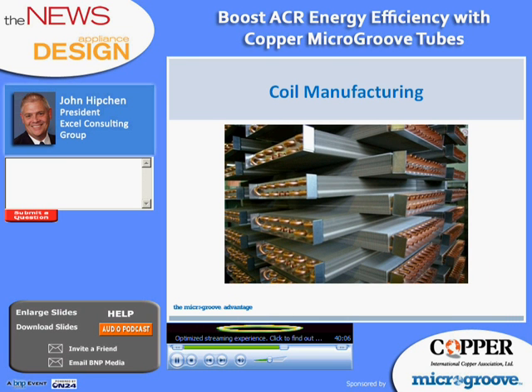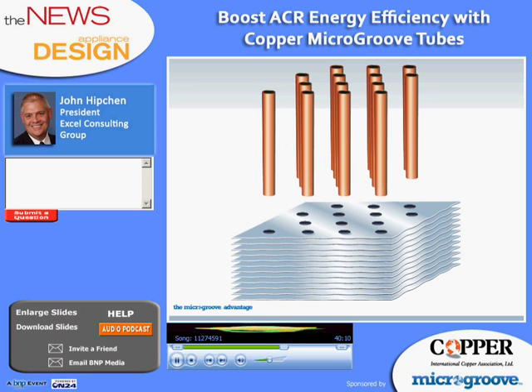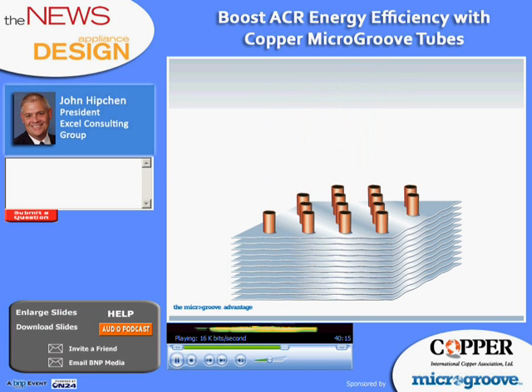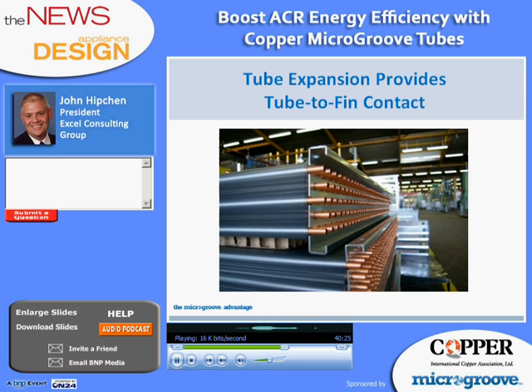So let me say a few words now about manufacturing practices. We all know that coils are made from tubes and fins, and we know that the tubes are inserted into the fins and then expanded to mechanically fasten the tubes to the fin. Tube expansion also ensures good contact between the tube and fin, and that's critical for the heat transfer that we need.